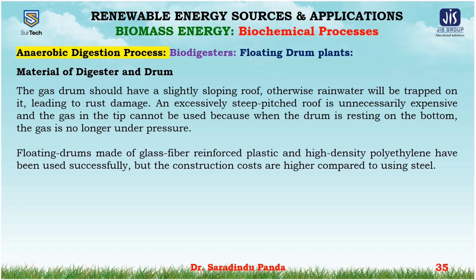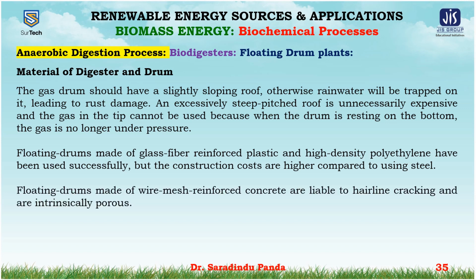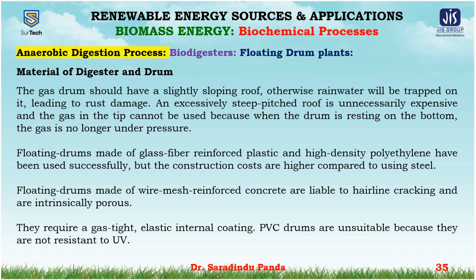The floating drums made of glass fiber reinforced plastic and high density polythene have been used successfully, but the construction costs are higher compared to using steel. Floating drums made of wire mesh reinforced concrete are liable to hairline cracking and are intrinsically porous. They require a gas-tight elastic internal coating. PVC drums are unsuitable because they are not resistant to UV.